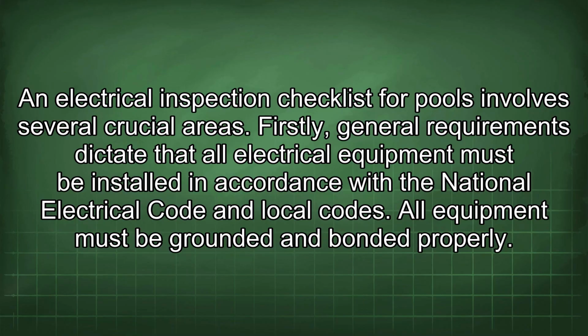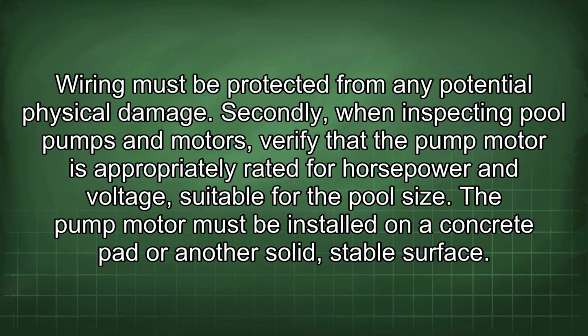Electrical inspection checklist for pools involves several crucial areas. Firstly, general requirements dictate that all electrical equipment must be installed in accordance with the National Electrical Code and local codes. All equipment must be grounded and bonded properly. Wiring must be protected from any potential physical damage.